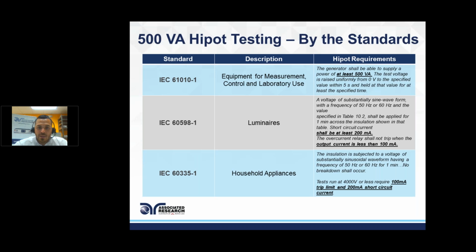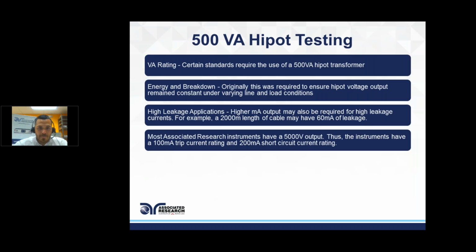They must pass the 200 milliamp short circuit test, meaning if that transformer alone inside your Hipot tester, forgetting firmware, forgetting any software control, if I short it, how much current can I get from it? And why do we want that? Well, I'll leave the slide here for you, and if you want to review it more, Brittany can send you a copy of it.